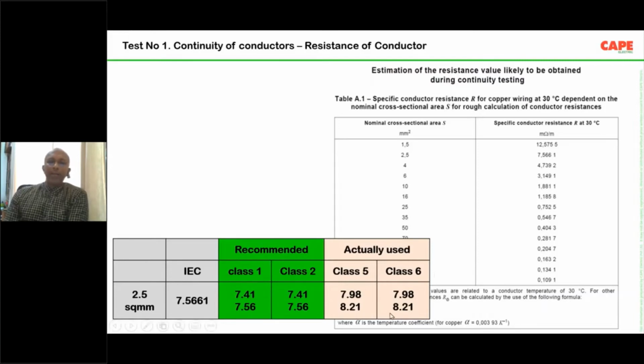There is one more conductor available, which is called class 6 conductor. This is nothing but the copper inside the welding wire, which is very much flexible. Now, what I wanted to tell you is, the IEC recommended value is 7.56. By using a class 2 conductor, that means a copper wire, PVC insulated, maybe FRLS, fire retardant or fire survival or whatever the insulation is, the copper in that particular conductor shall offer this much resistance. This is what is recommended in IEC and used worldwide.